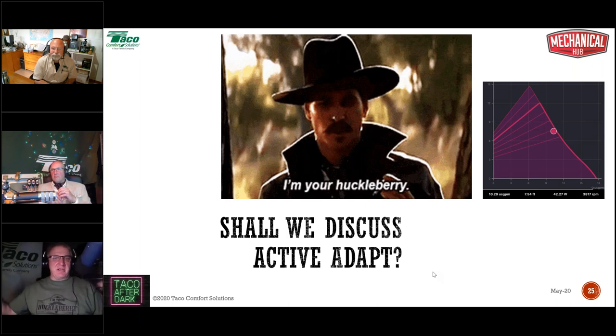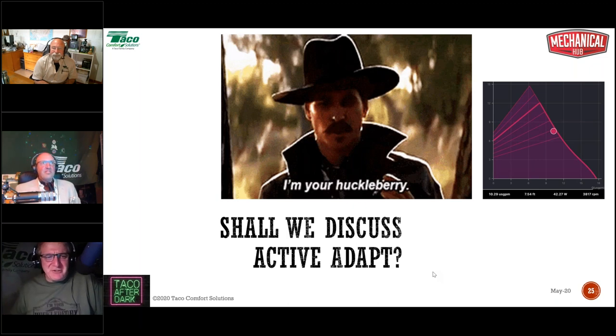People talk about, well, as it gets warmer out, the delta T gets smaller, but that's important because you've got to have some heat. And they talk about lowering flow rates and all that other nonsense, which is technically correct, but we've got minimum speed, man. Let's not forget that. So really, a long answer to a short question, there is no effect. Delta T doesn't affect outdoor reset. Outdoor reset doesn't affect delta T pumping. If you truly understand what delta T pumping is trying to do, it's clear there's no fighting going on here. Alrighty then.